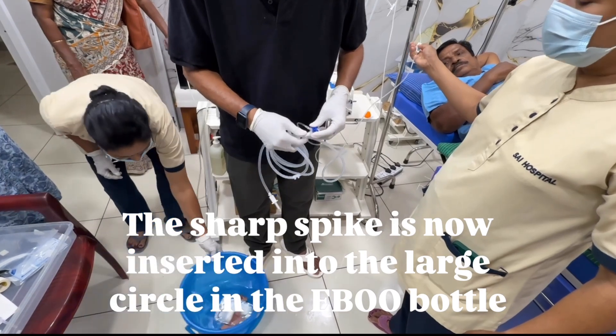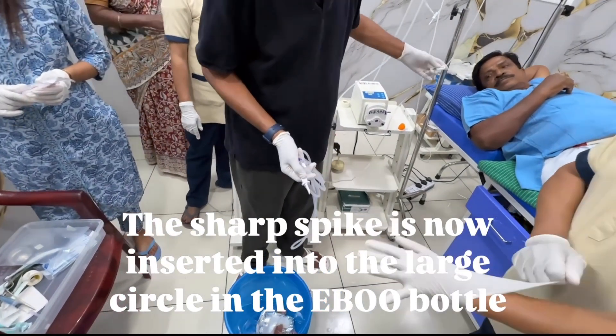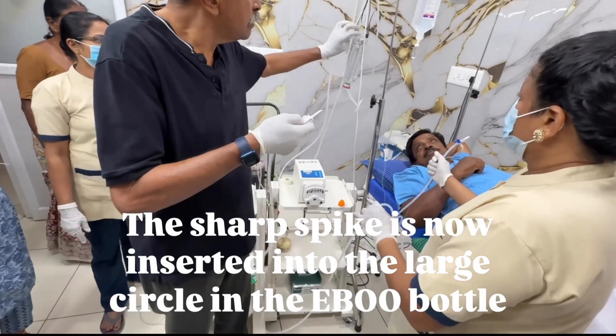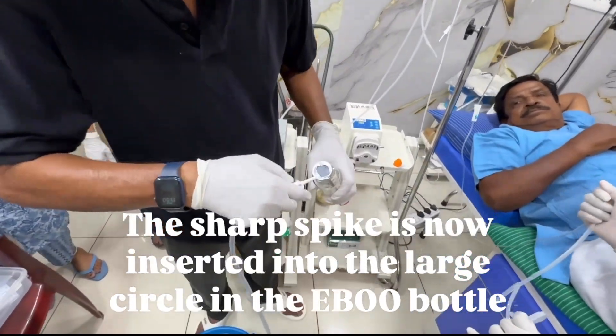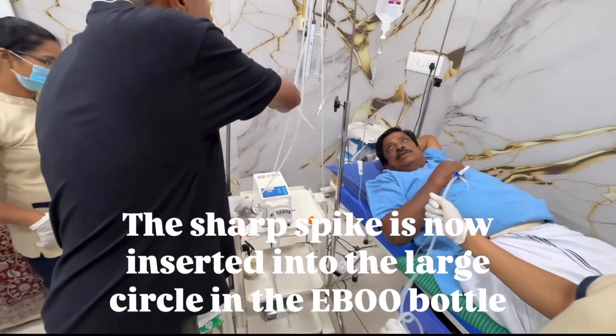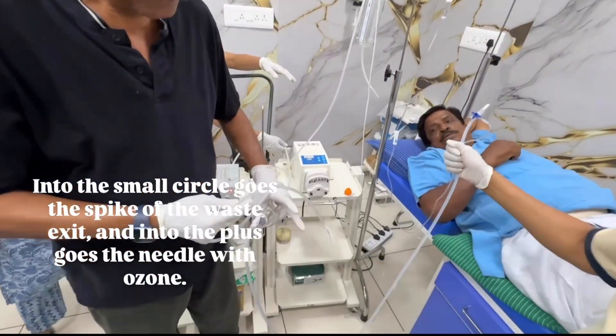The sharp spike is now inserted into the large circle in the EBOO bottle. Into the small circle goes the spike of the waste exit, and into the plus goes the needle with ozone.